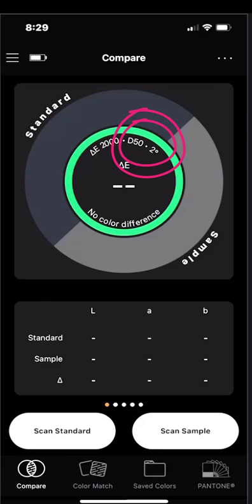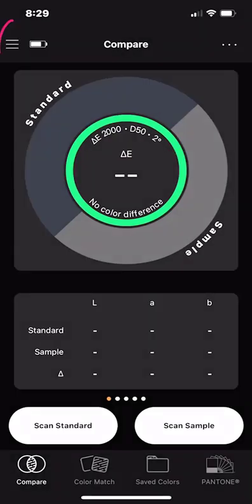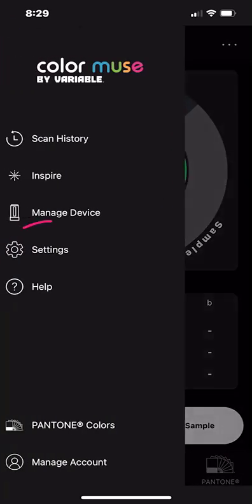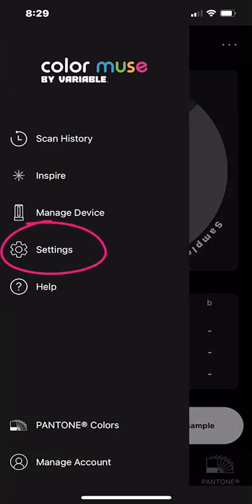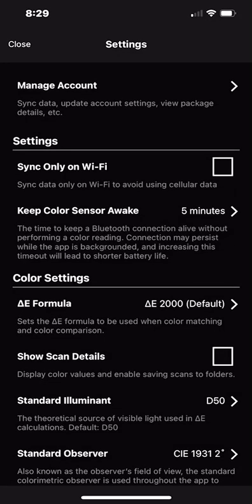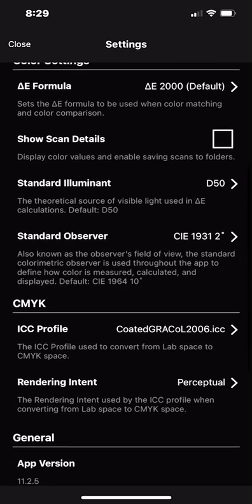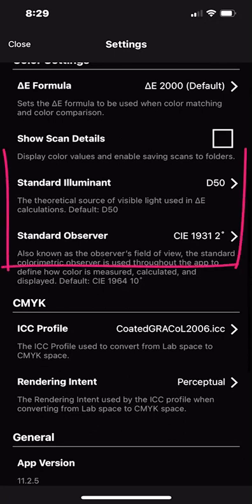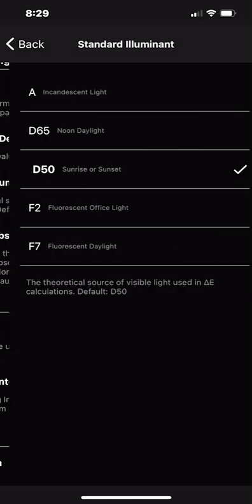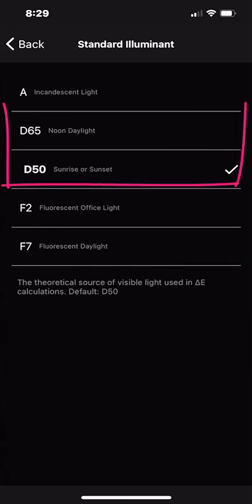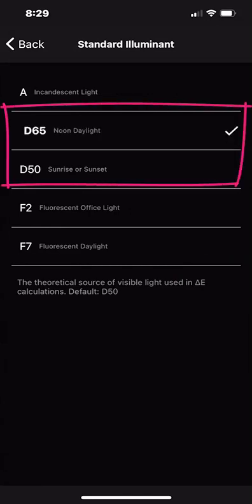We do that by tapping the hamburger in the upper left hand corner. In the next window choose settings and if we scroll down a bit we can see that the illuminant and the observer settings are right about here. Again we need to change D50 to D65. When we're done doing that we can tap back.